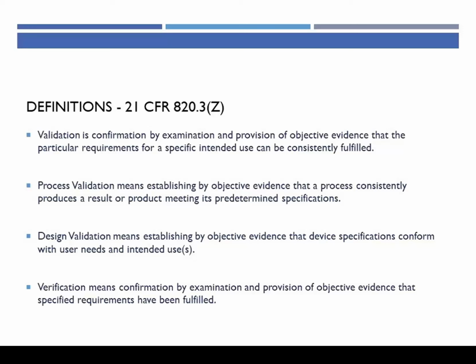Now, process validation is a specific case of validation. It means establishing by objective evidence. So there's again the requirement for proof. But here's where it's different. Here we want to see that a process consistently produces a result or product meeting its predetermined specifications. So this is showing that your manufacturing processes produce acceptable product.